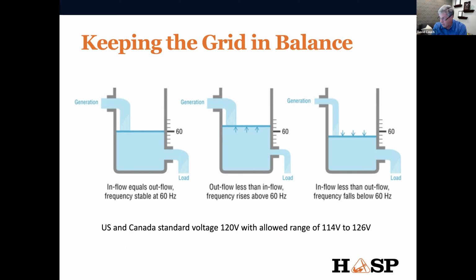But if you're generating more electricity into the grid than the load can consume, the frequency goes up. If it goes to a certain point, your devices will start to fail and circuit breakers will pop, because systems aren't designed for anything greater than 60 cycles per second. Likewise, if you aren't generating enough and there's more load demand, the frequency goes below 60 cycles. We'll see that specifically when we talk about Texas.